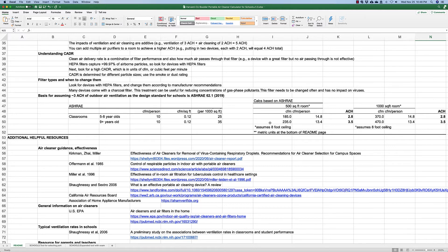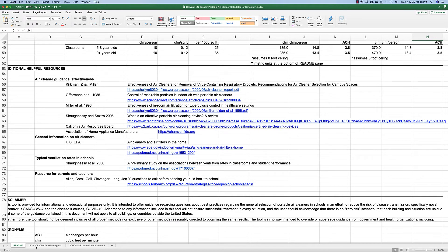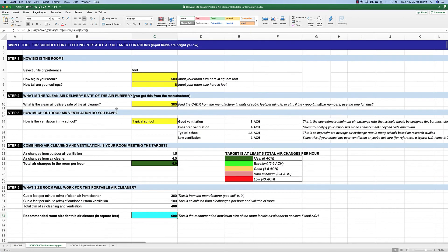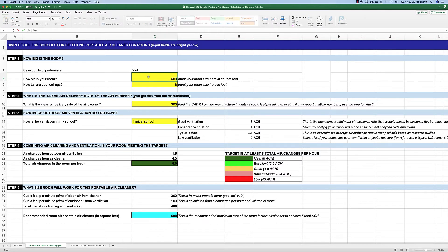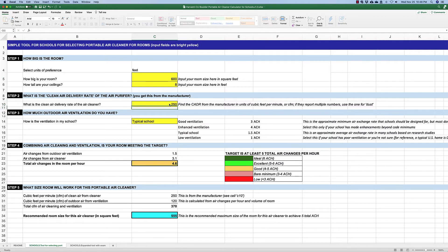The second tab in the spreadsheet is a tool for selecting your portable air cleaner. You will enter information into the bright yellow fields, and all the other fields will help inform your decision. First, enter the size of the room — I'm going to change it to 600 square feet with an 8-foot ceiling. I've located an air cleaner with a clean air delivery rate of 250 cubic feet per minute.